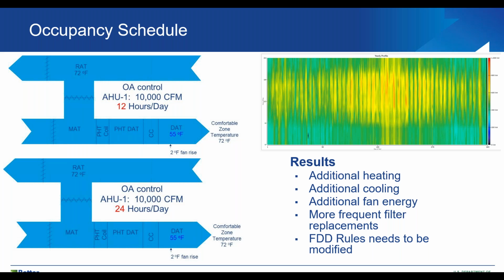Now we're operating under COVID, and one of the options is to run 24 hours a day. So the facility staff will either make the changes themselves or work with the BAS vendor to change the operations of the air handler to run 24 hours a day. So what happens then? You may be using more heating, cooling, and fan energy. The filters will require more replacements more frequently. And the FDD rules now need to be modified, because if they aren't, it's going to be flagging all the time that the system should be off.